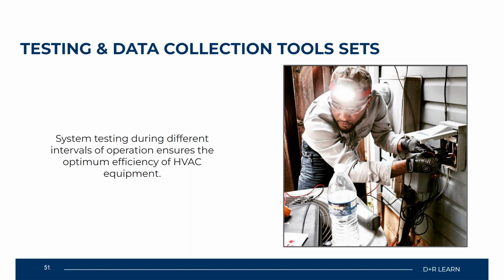So faults and other operation halting issues, like I mentioned, can be discovered and addressed before any bigger problems can arise. So you want to make sure you're following up with manufacturers' recommendations as far as inspections and servicing per the specific interval, whether that's a daily, a weekly, a monthly, a quarterly, a semi-annual or an annual type of inspection or service. These have to be done for all these different systems, or you're going to run into a lot of different problems. So we're going to touch a little bit on some of these different instrument testing methods and the actual instruments themselves. And on Thursday, we're going to continue that conversation.